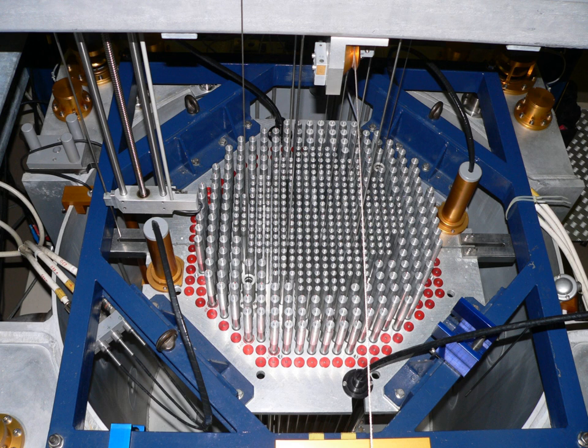If the coolant is a moderator, then temperature changes can affect the density of the coolant/moderator and therefore change power output. A higher temperature coolant would be less dense, and therefore a less effective moderator.